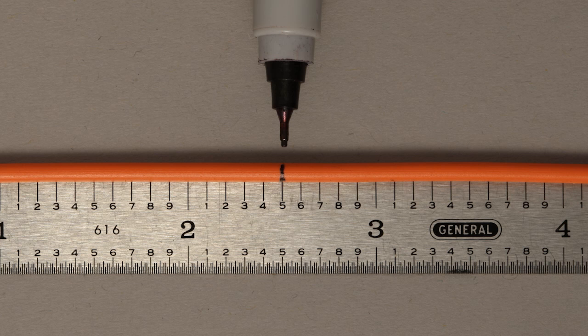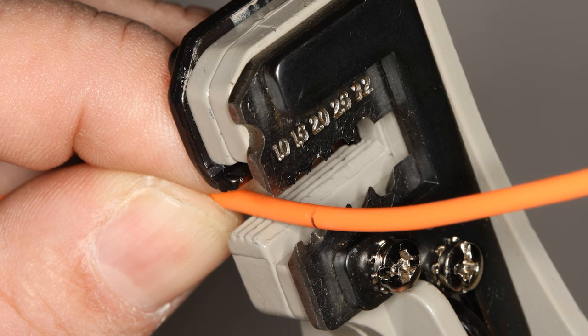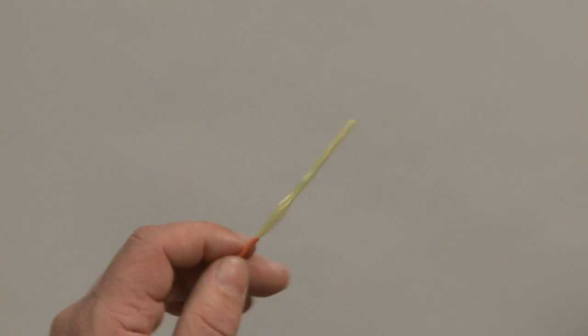Mark the outer jacket of the fiber optic cable at two and one half inches. Select the correct hole in the cable stripper for the size of the outer jacket of your cable. Strip the outer jacket at the two and one half inch mark or in shorter sections to make removal easier.